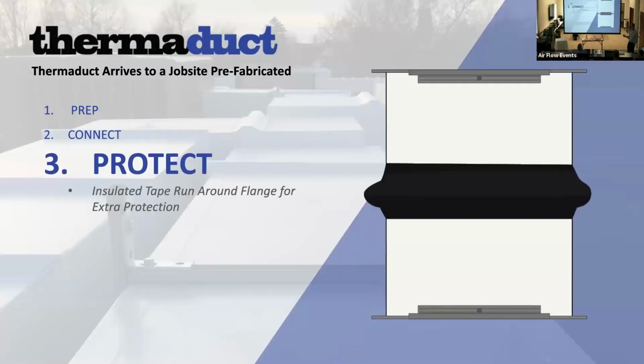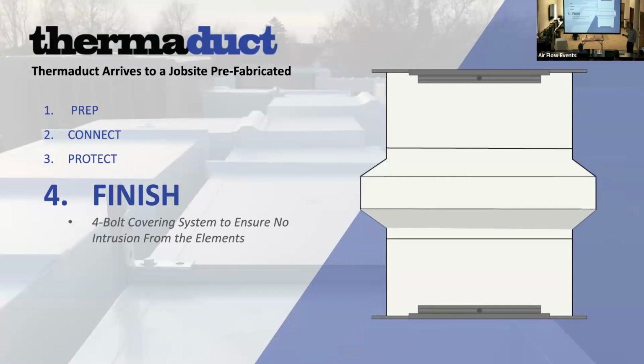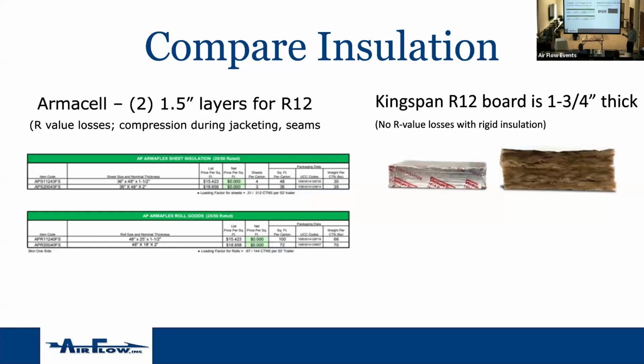Prep, connections, then there's what Thermaduct calls an insulated tape, and then the cover. Okay. I think I built this a little while ago. I think what I was doing is just showing insulation's not that cheap. It is more expensive to buy Thermaduct than it is to put in metal and then get the insulator to come out, but if you specify mineral wool and peel and seal, it's going to be cheaper. If your insulation is more rigid, like rigid board and a higher grade, then the gap narrows between the two. And of course, it doesn't compress and all that other good stuff that we talked about.